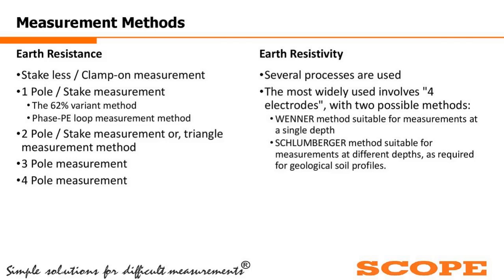One is without signal injection, which means we measure whatever earth leakage current is flowing into the circuit or to the ground, and from that we calculate the earth resistance or the earth pit resistance. And there is one more option, where we put in an external signal generator, or current injector, an AC injector, and then use the stakeless or clamp-on measurement to understand the value of the earth pit. Then comes one pole or single stake measurement. Here onwards we are using the 62% variant method. These methods I will cover in detail in the subsequent slides. And the second way of single pole or single stake measurement is the phase to PE earth loop measurement method.